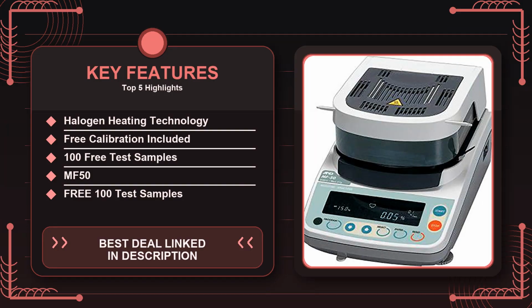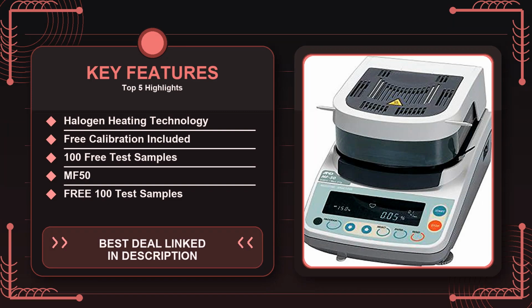First off, think about the typical scenario where you actually need a moisture analyzer. In my experience, the most common use cases involve testing raw materials. Think plastic pellets, powdered chemicals, or food ingredients to verify that they meet specification limits before they go into production. In those moments, you're not looking for a device that can give you a 10-point curve of moisture loss over hours. You need something that can tell you, within a few minutes, whether the sample is at 0.5% moisture or 2% moisture, and do it consistently.